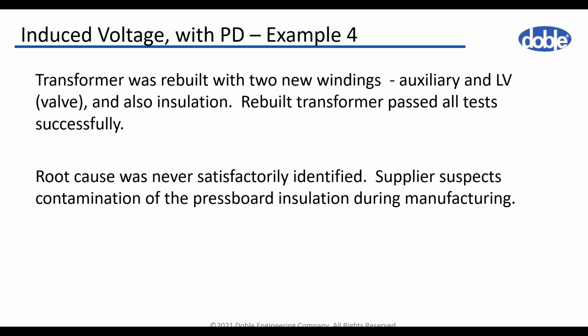The manufacturer suspects that some contamination in that area caused the problem and the breakdown, actually. We believe that this definitely is not a design issue, because this was one of the last of a total of 12 transformers of the same design tested, and all of them passed the test successfully. The winding was rebuilt, and the transformer was then retested again. It passed all the tests successfully.